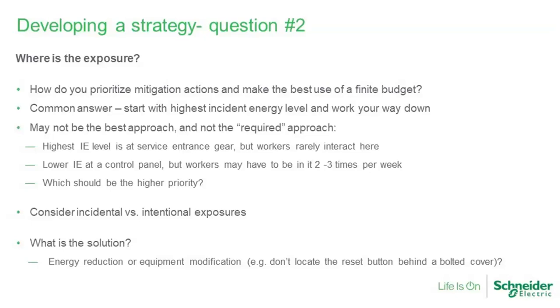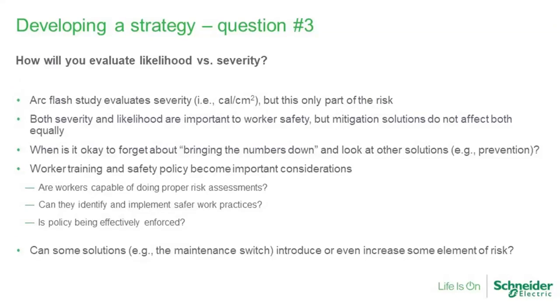So again, a little bit different consideration than we look at times. Question number 3, how will you evaluate likelihood versus severity? And this gets back to what we were talking about earlier with the two aspects of safety, the probability versus the level of hazard. In a lot of cases, what we find is that if we look at a potential solution, if you can't reduce the incident energy level, if you can't reduce that calorie per centimeter squared value that's shown on the arc flash label, people lose interest in it, right?